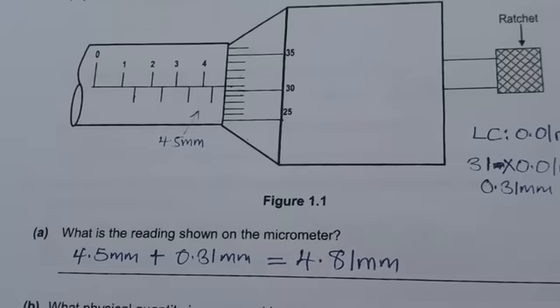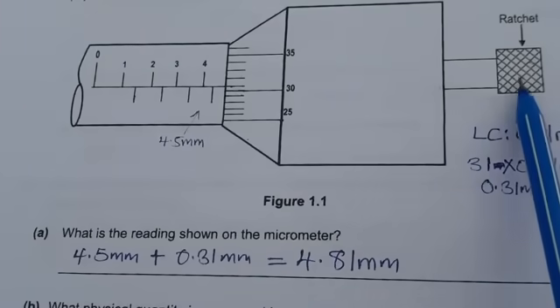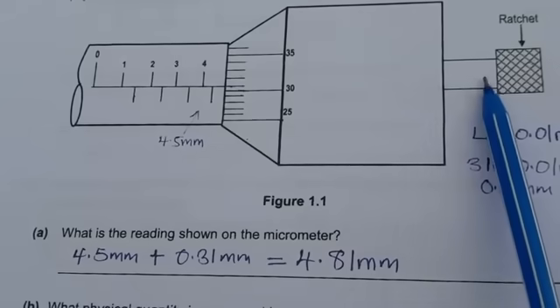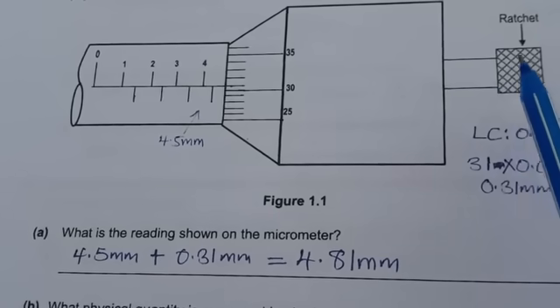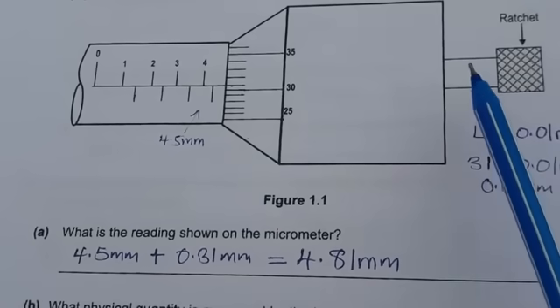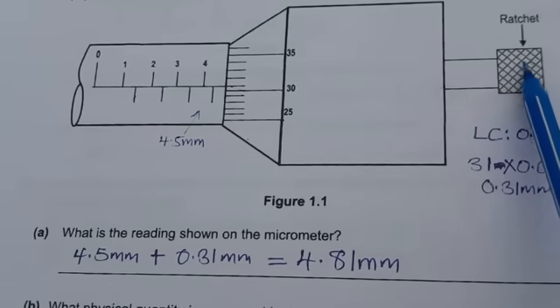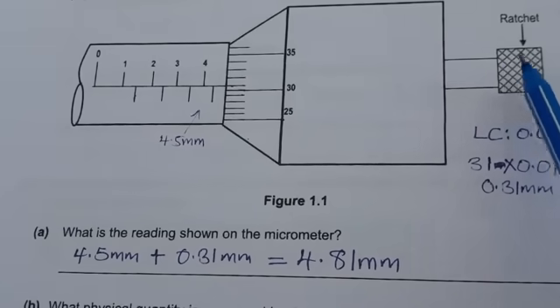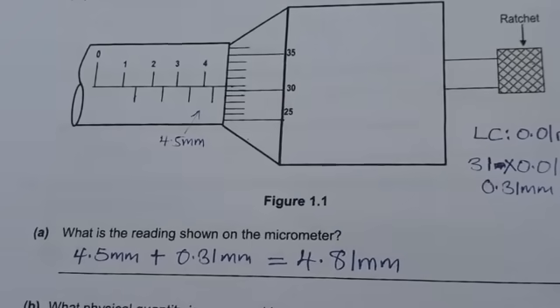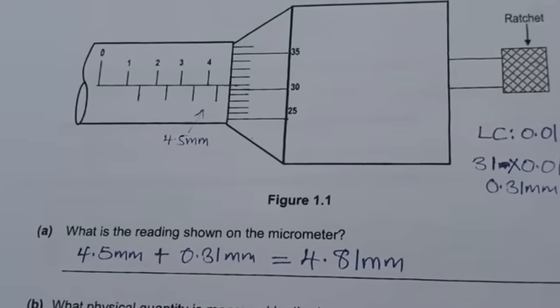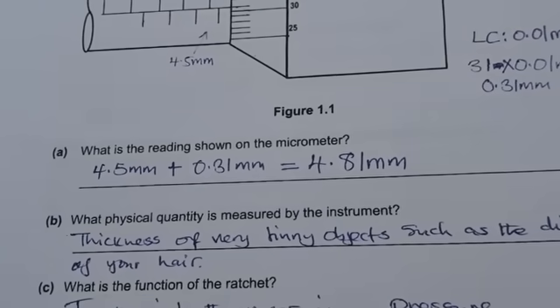This instrument is very delicate, very fragile. If you apply too much pressure when taking your measurement, you may damage the instrument. So this ratchet is used to maintain the measuring pressure. There is a certain sound that the ratchet makes to say you are not supposed to go over this pressure that you are applying on the instrument.